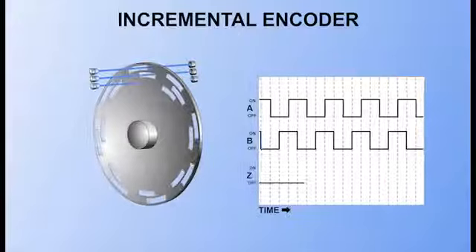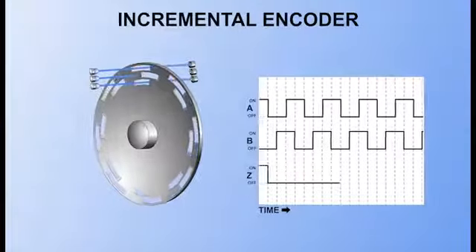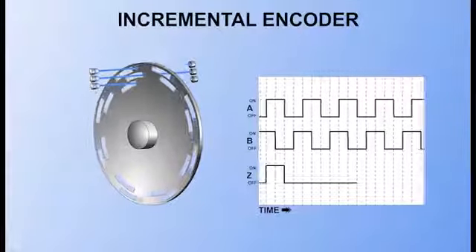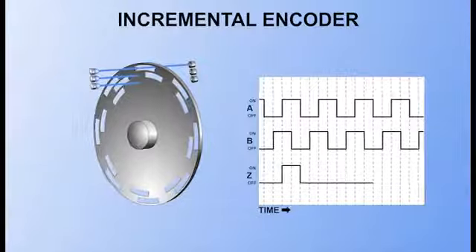If desired, a third track with a single pulse, called track Z, may be added. This track may be used to produce one pulse for each complete revolution of the encoder wheel. The Z track is often used to reset pulse counters each revolution.